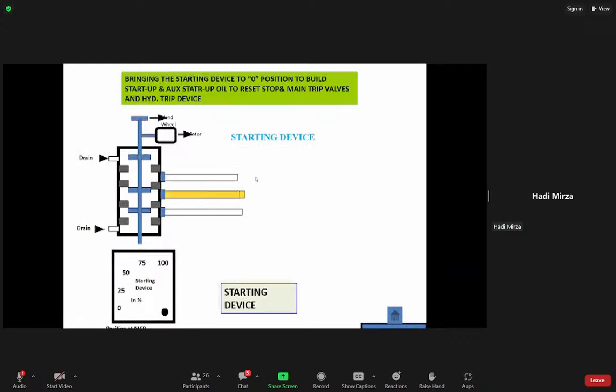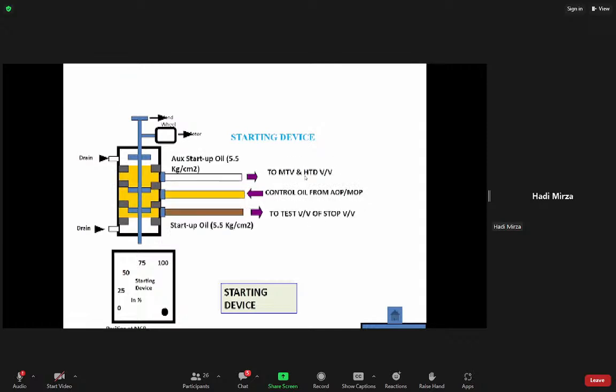When you bring it to the 100 to 0 position, startup control oil comes in between the ports, and then the auxiliary startup will generate from here, and it will go to the main trip valve and the hydraulic trip device, that is the overspeed trip release device. To reset the test valve and stop valve, it will go from the bottom of the starting device.